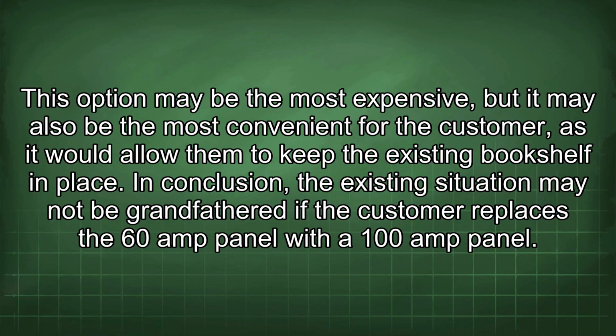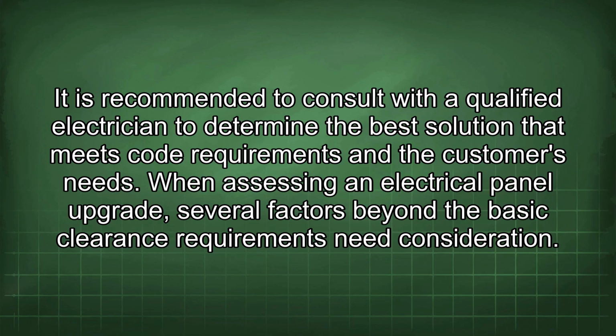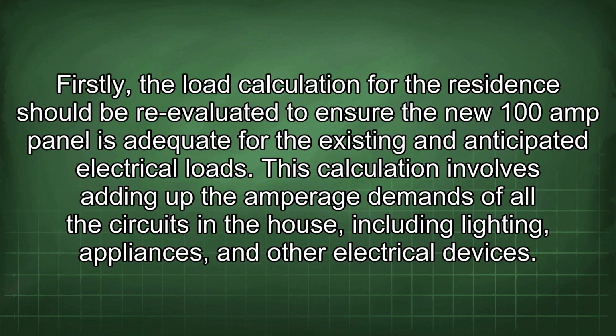In conclusion, the existing situation may not be grandfathered if the customer replaces the 60-amp panel with a 100-amp panel. It is recommended to consult with a qualified electrician to determine the best solution that meets code requirements and the customer's needs. When assessing an electrical panel upgrade, several factors beyond the basic clearance requirements need consideration. Firstly, the load calculation for the residence should be re-evaluated to ensure the new 100-amp panel is adequate for the existing and anticipated electrical loads.